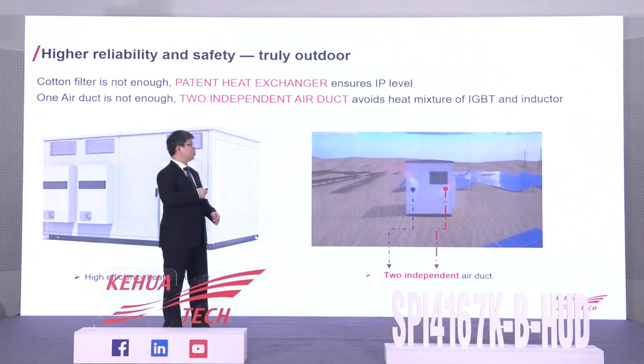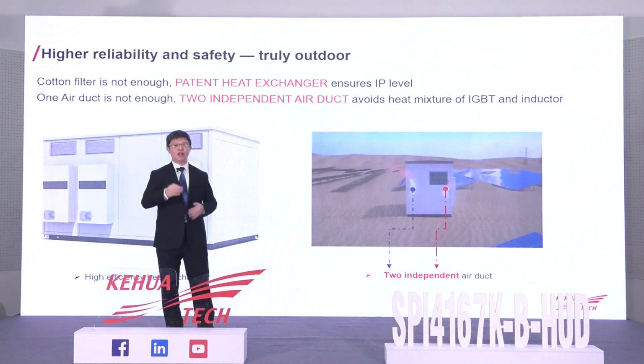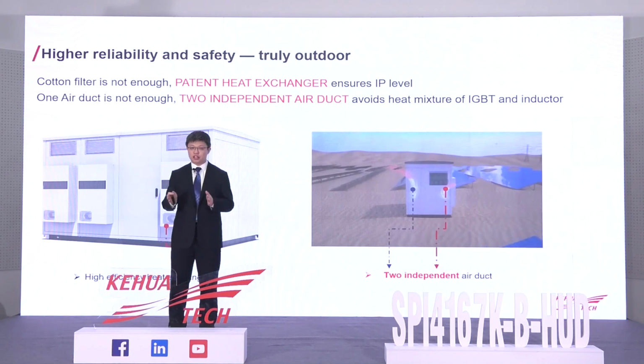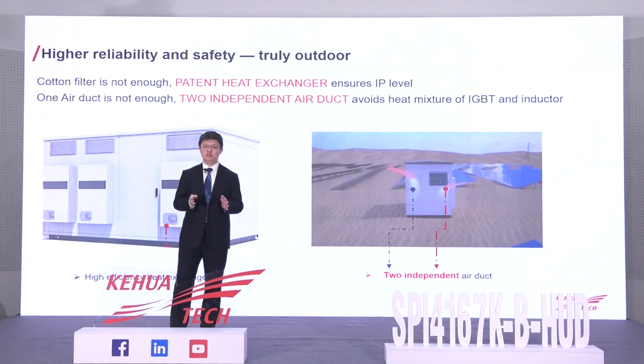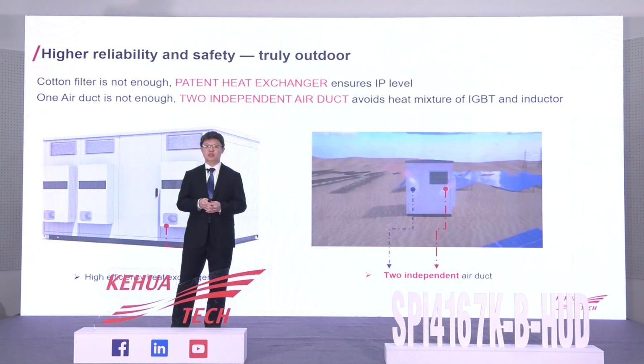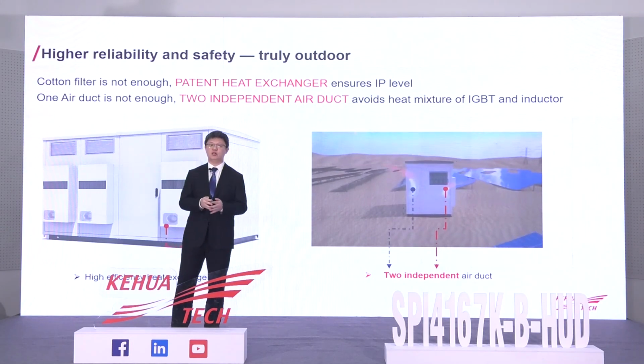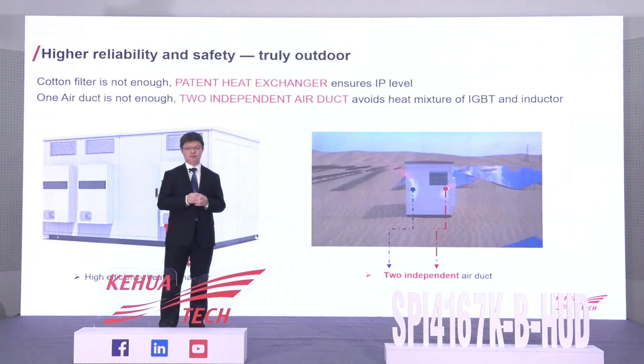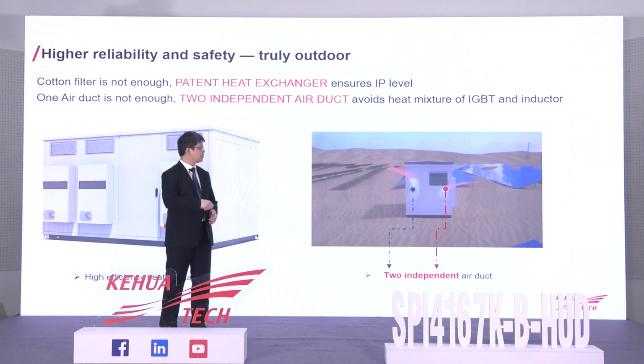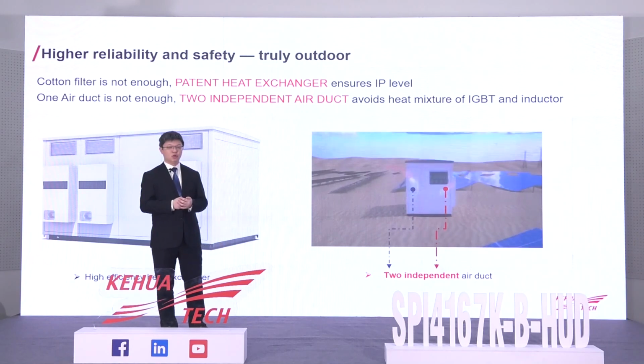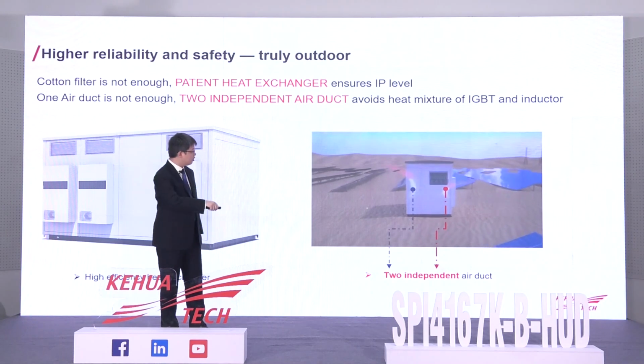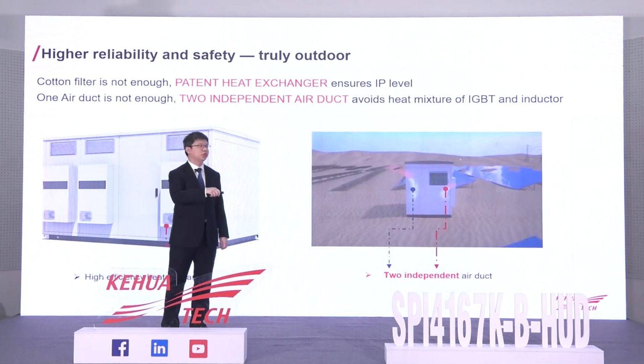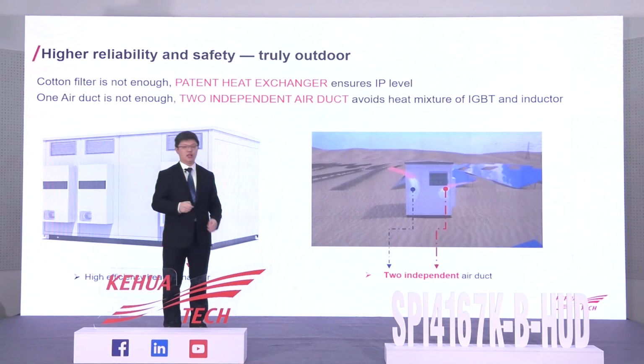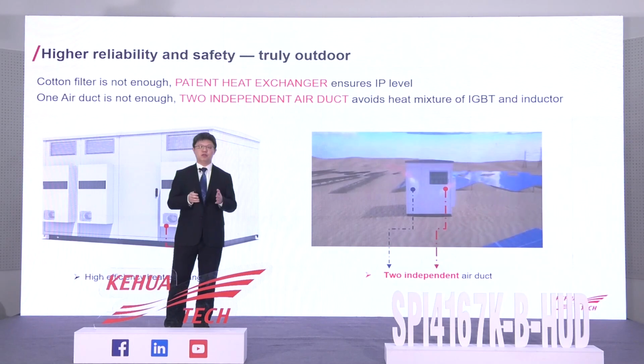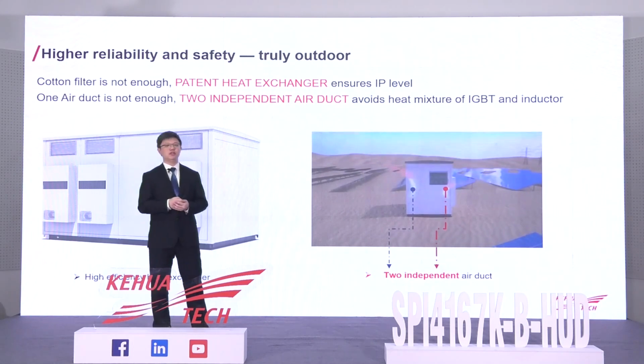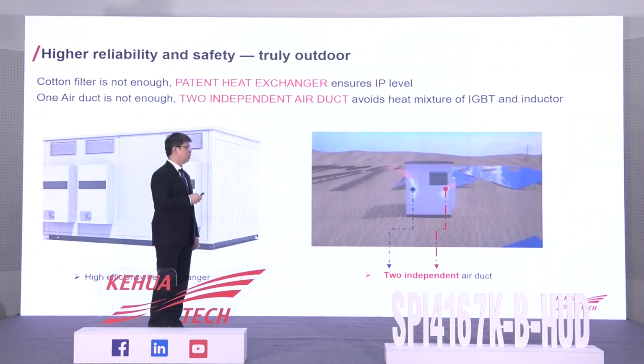Most central inverters still use cotton felt for the IP level and one air duct for airflow. For a truly outdoor inverter, is this enough? The patented heat exchanger solution developed by Kehua replaces the cotton felt, and the two independent air ducts avoid heat mixing, as you can see in this picture on the right. We don't need to worry about hot air from the inductor going directly to the IGBT and affecting its life cycle and reliability. We are very confident that this patented heat exchanger and two independent air ducts ensure truly outdoor application.